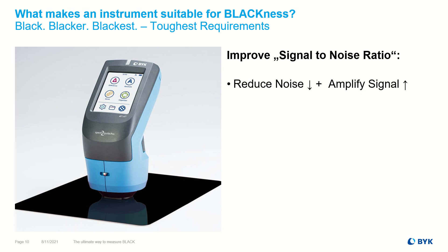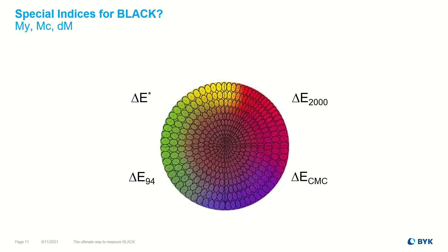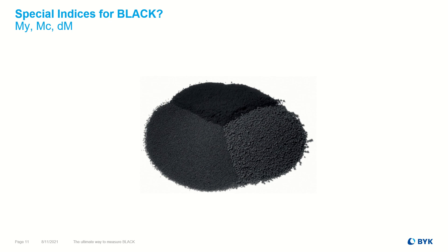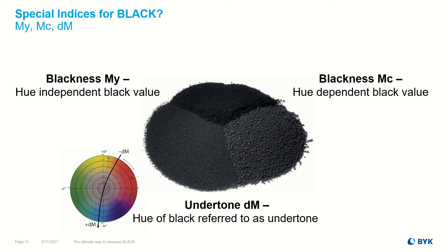In summary, a reduction of noise and amplification of the signal leads to an improved repeatability and inter-instrument agreement. Instead of the usual CIELAB values, special indices were developed and published in ISO standards to measure black to achieve a better visual correlation. M-Y describes the blackness of a sample independent of the hue or undertone. M-C describes the degree of blackness dependent on the colored undertone. D-M describes the hue of black referred to as undertone.